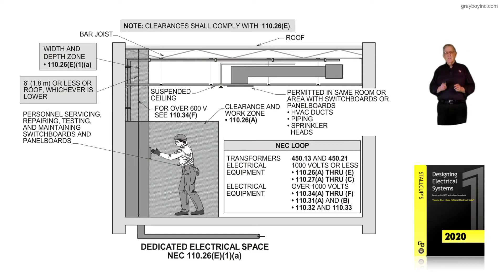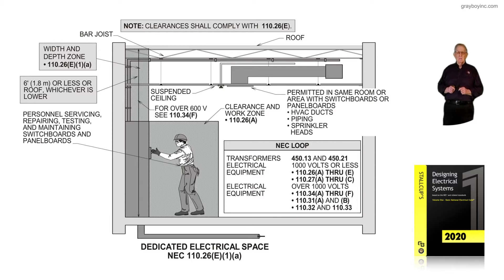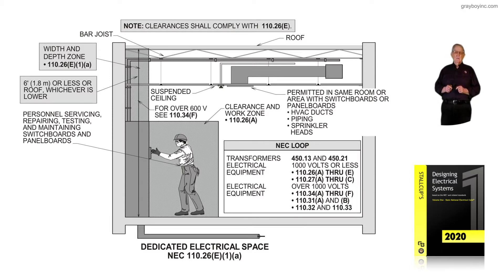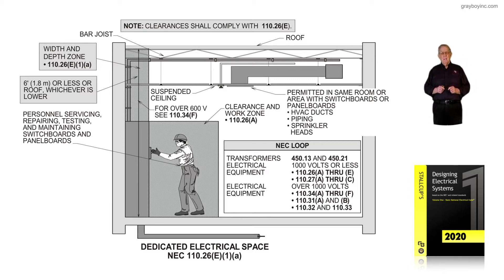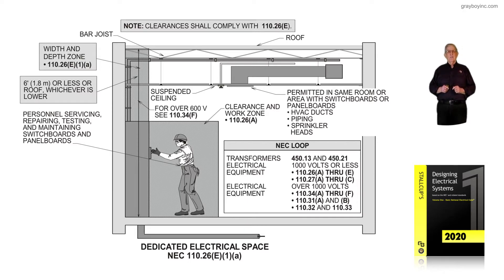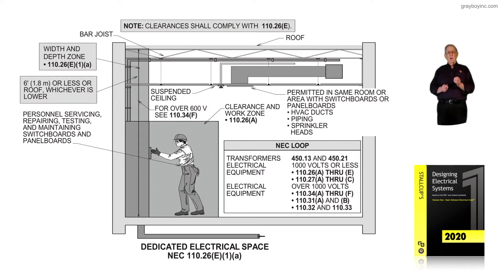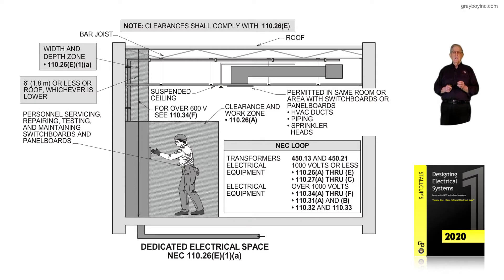This illustration is talking about dedicated electrical space in accordance with the NEC, 110.26, E as in Ed 1, little A. Notice in the illustration, it's kind of busy, but it lists important requirements that we would need to look at. The note says clearances shall comply with 110.26E.